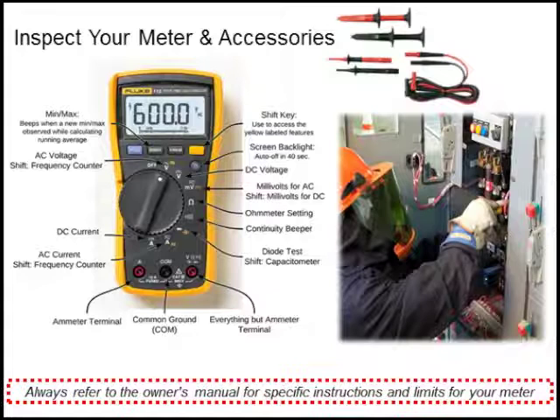Another common mistake I want to point out here is many meters have what's known as a hold button. You want to make sure that's not locked in, because if it is, you'll be getting invalid results from your test. Hopefully we all agree that the days of checking for voltage with wet fingers is behind us. We're going to use a quality meter. Here we see a picture of an individual who's properly equipped and prepared to go in and do our voltage testing.